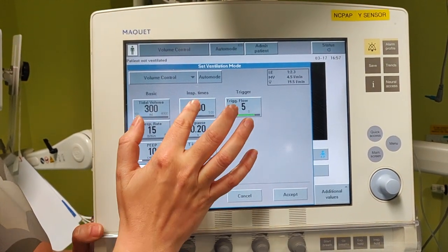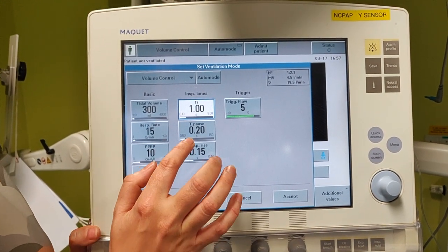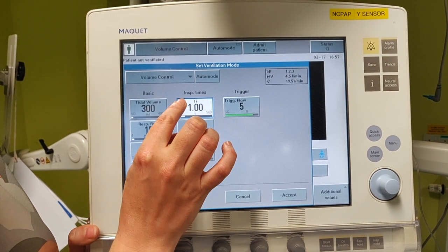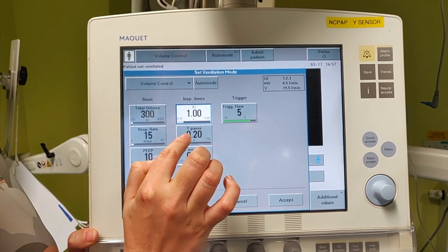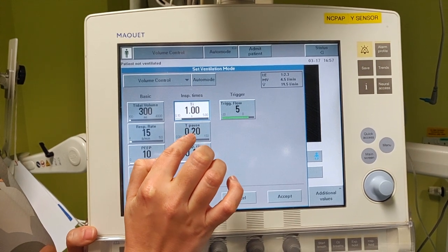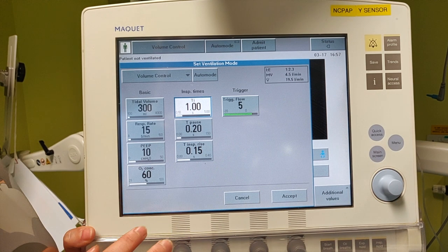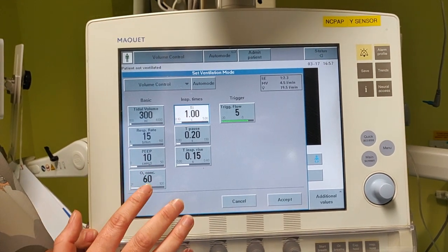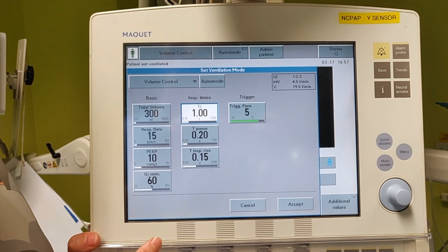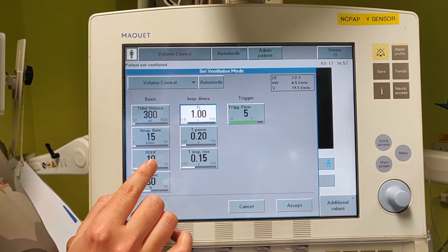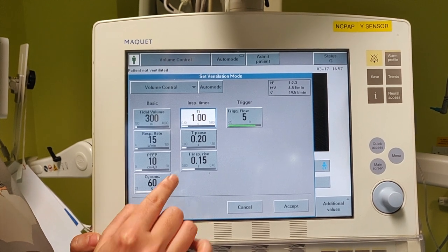What are we going to do with the inspiratory times? Volume control has a particularity — it has an inflow inspiratory time and also a pause time when the ventilator stops in inspiration and the air redistributes. Not going to go through the debate of whether this pause time is really needed or not, but if you set up one, you're going to have a lot more monitoring tools available than if you don't.